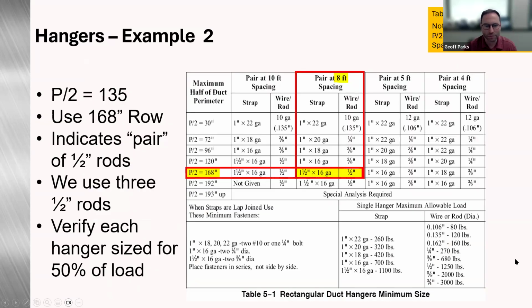So now that we have that information, we can come to table 5-1. Our half perimeter was 135. So, checking out the P divided by 2s, we have to go to 168 here because 120 is not big enough. So we would use the 168 row, and this indicates that we need a pair of 1/2-inch rods. For this one, we're going to use 3 rods. And then basically you just need to verify that each hanger is sized for 50% of the load.